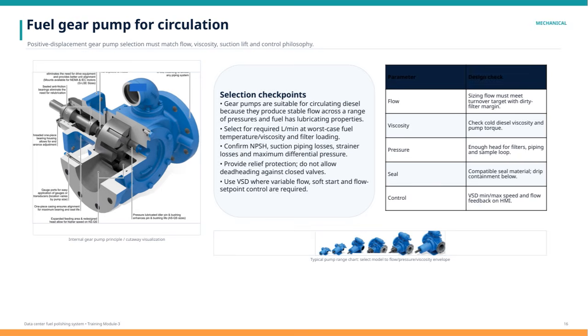interface screen. Looking specifically at design checks, the pump must deliver the correct flow with some margin for dirty filters. We check cold diesel viscosity to understand required pump torque, ensure the pressure head is sufficient for filters, piping, and any sampling loops, and verify compatibility of seal materials with proper drip containment. To visualize the selection process, imagine a chart showing pump models across different flow rates, pressures, and viscosities. Selecting the right model means choosing one that fits within the operational envelope for your specific conditions. Overall, careful attention to these selection checkpoints helps guarantee reliable pump performance in the data center fuel polishing system.